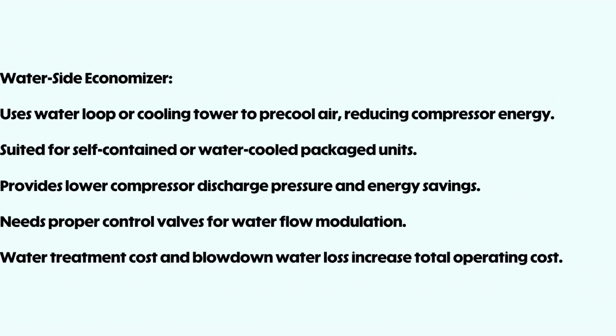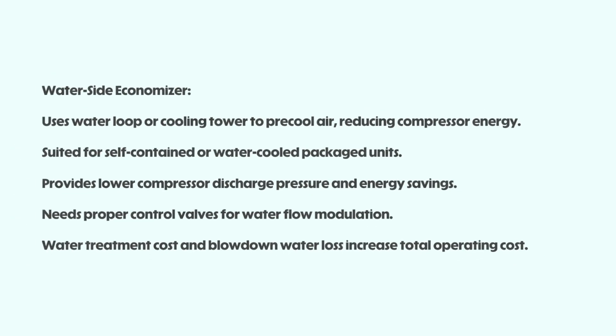The water-side economizer achieves the same goal using chilled water from a cooling tower or evaporative system to pre-cool air. When outdoor wet bulb temperatures are low, this system can maintain supply air temperatures without mechanical cooling. Benefits include reduced compressor load, lower discharge pressure, and decreased energy use, but water treatment and blowdown increase operational costs.